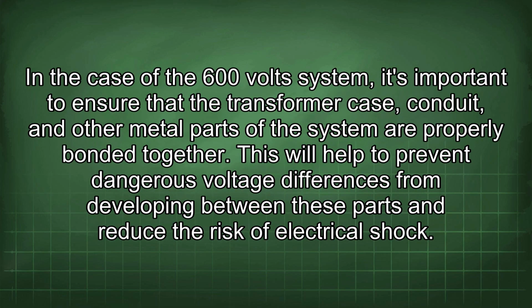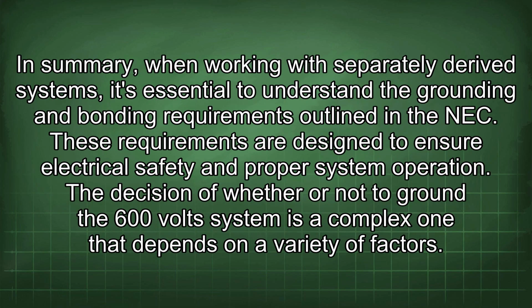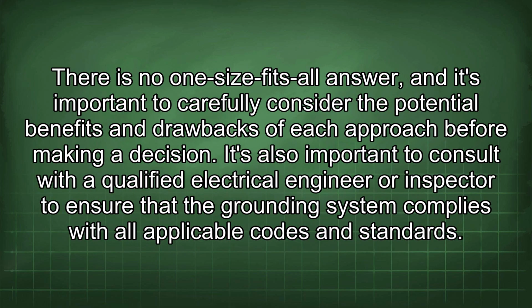In the case of the 600-volt system, it's important to ensure that the transformer case, conduit, and other metal parts of the system are properly bonded together. This will help to prevent dangerous voltage differences from developing between these parts and reduce the risk of electrical shock. In summary, when working with separately derived systems, it's essential to understand the grounding and bonding requirements outlined in the NEC. These requirements are designed to ensure electrical safety and proper system operation. The decision of whether or not to ground the 600-volt system is a complex one that depends on a variety of factors. There is no one-size-fits-all answer, and it's important to carefully consider the potential benefits and drawbacks of each approach before making a decision. It's also important to consult with a qualified electrical engineer or inspector to ensure that the grounding system complies with all applicable codes and standards.